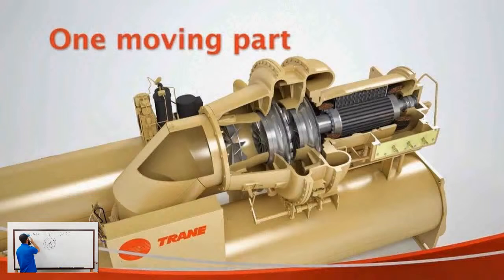So, for example, if you're below set point or above set point, especially by 1 or 2 degrees, unless you are having some kind of limiter, which should be displaying on your chiller controls, you should be able to physically watch that armature swing those PRVs one way or the other. So if you need to unload the machine, they're going to close. If you need to load the machine to pull the water down further, you're going to see them open.